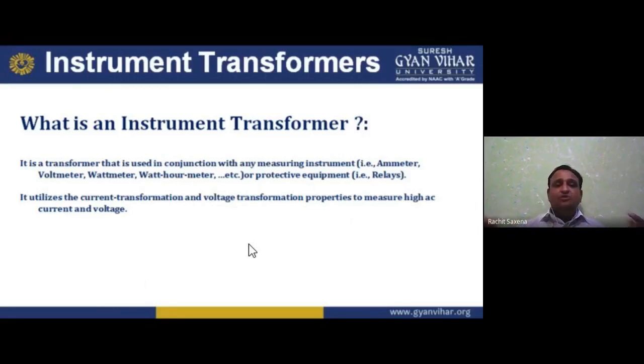So it utilizes the current transformation, obviously. How are we using the current transformation now? See, in a transformer we have K, the transformation ratio, which is always equal to the ratio of secondary voltage to primary voltage, primary current to secondary current, we can say, and secondary turns to primary turns. So V2 I2 is equal to V1 I1. So we can say V2 by V1 is equal to I1 by I2 is equal to N2 by N1. That is your K, the transformation ratio. So we use current transformation and voltage transformation.